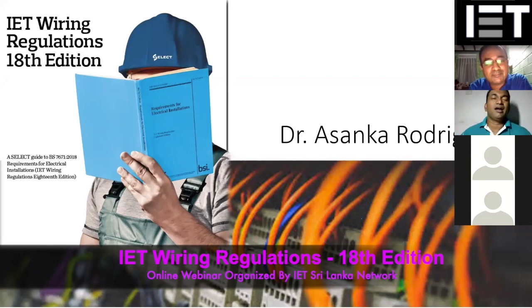Dr. Asanka: Yeah, actually, bathrooms are considered special locations. When you look at special locations, these bathrooms are layered in such a way that there are zone 1, zone 2, zone 3, and the outside zone. Especially in the shower area, we consider it zone 1. Then, if I remember the correct value, about 1.25 meters away from the bath or shower is zone 2, and then 2.25 meters away from zone 1 is zone 3, then the outside zone. In the outside zone you can install any equipment, but in the zones you cannot use normal equipment. Especially in zone 1 and zone 2, you have to use special equipment.